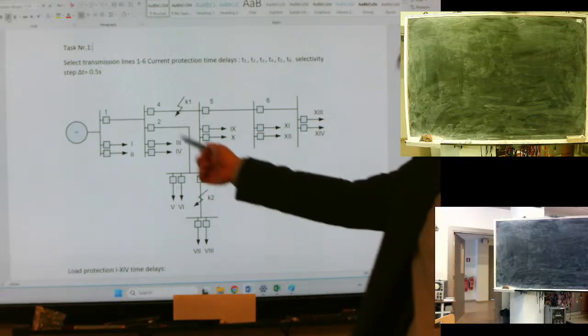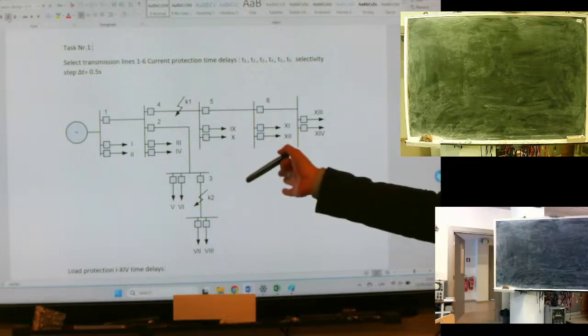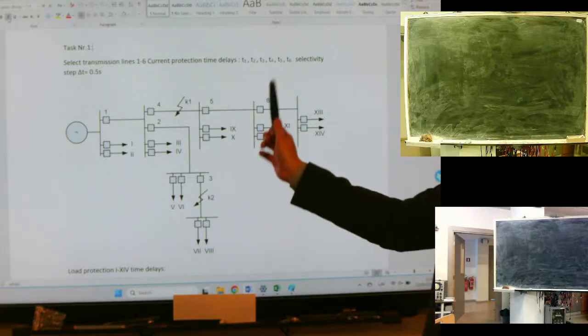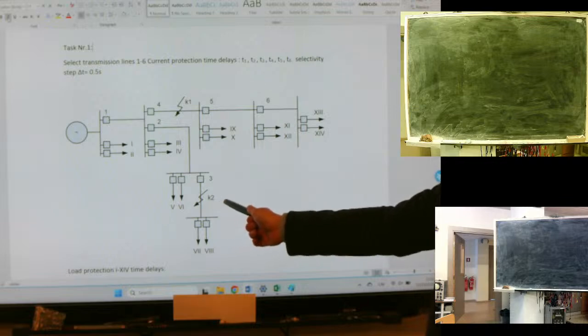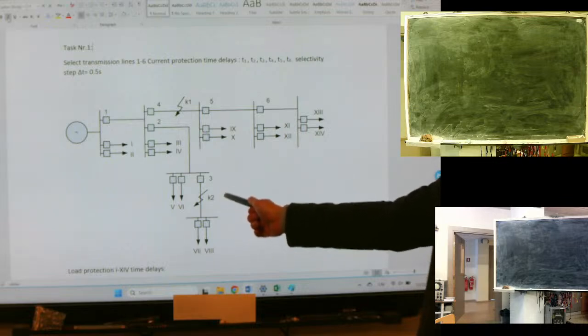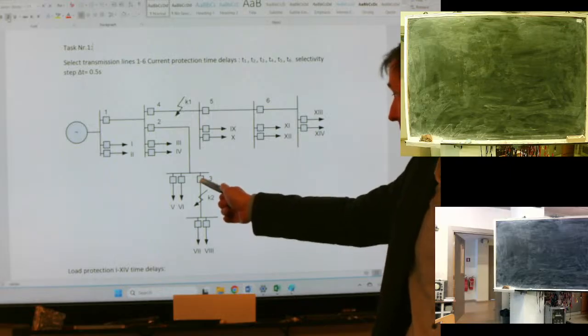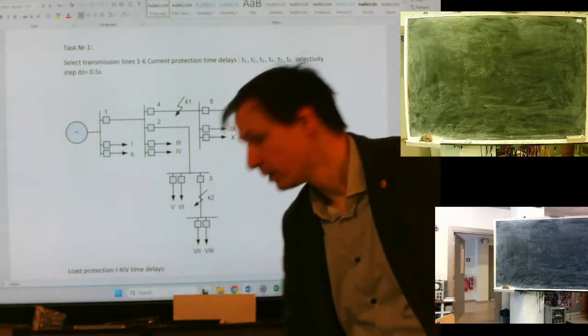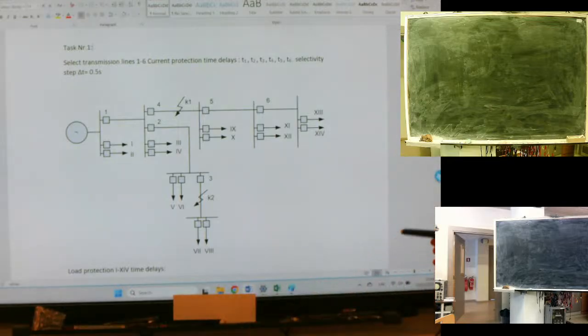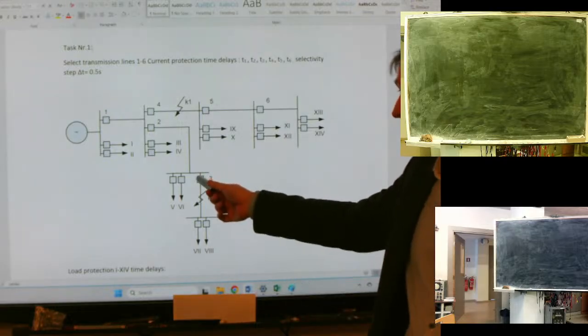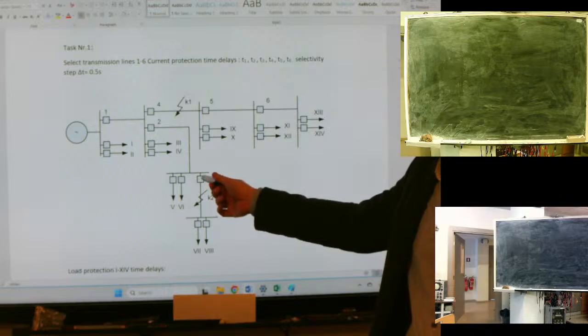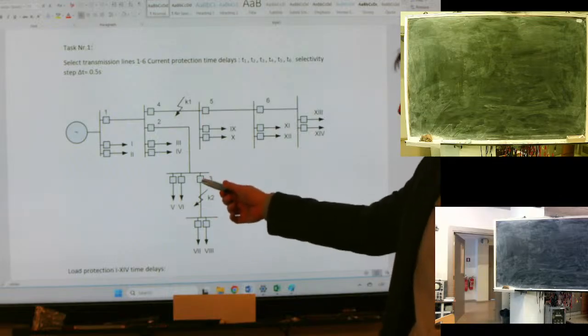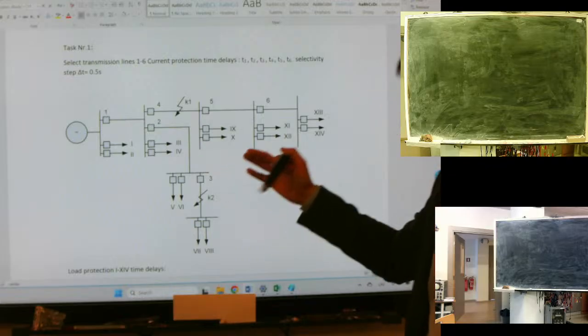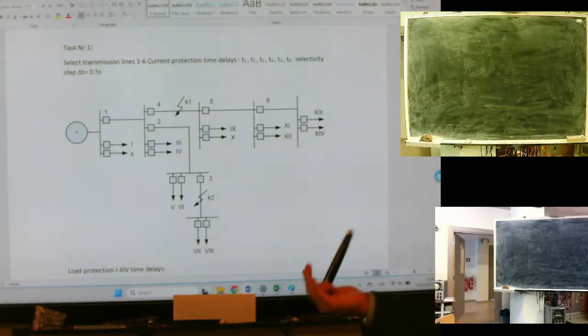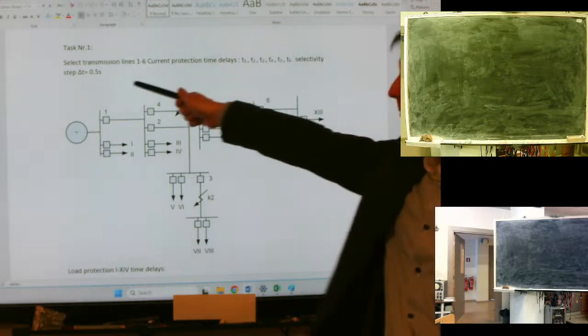So all relays in series could detect this current, but the command for disconnection will be for relay number 3 first, then second, and third. How could we make this? Using time delays. So put a time delay here. Of course, it depends on our possibilities. What will be the selectivity step?